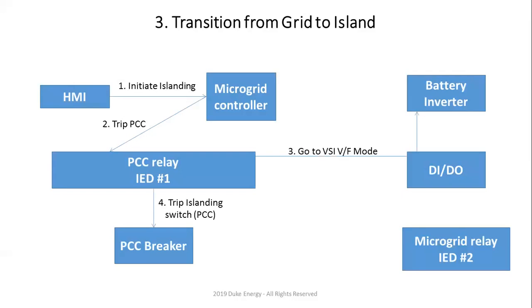There's about 4 to 6 cycles, depending on what kind of recloser breaker you use. There's about 4 to 6 cycles that it takes to break the arc and everything else. At that time, when we open, we send the confirmation to the battery inverter that we are open. Essentially, the battery has to switch from the VSI VF mode to the VSI ISO mode. VSI ISO mode is the islanding mode.